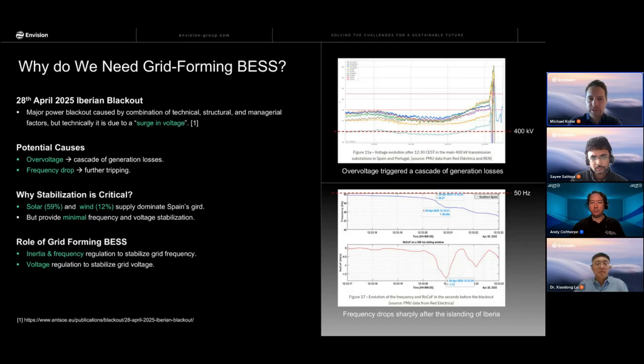If you look at it more concretely, what were the technical causes in Spain? So we have overvoltage. That's something grid forming can help with in terms of voltage regulation with reactive power and other elements we'll see in detail. We have a rapid frequency drop, so a high rate-of-change-of-frequency event. Of course, that's somewhere where virtual inertia based on grid forming technology can play a role.